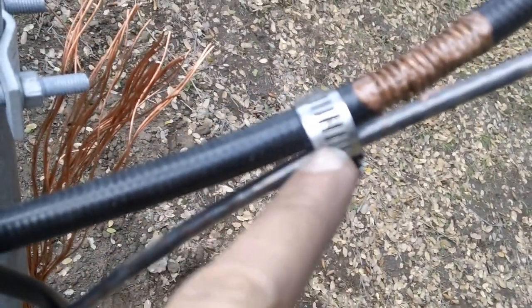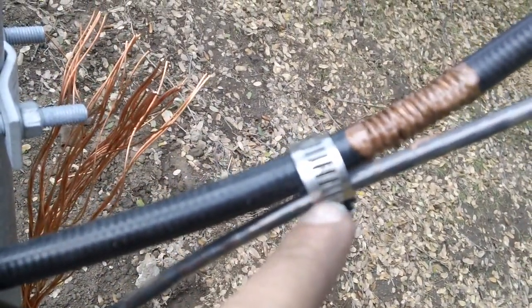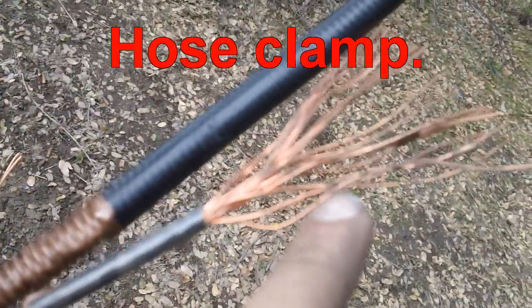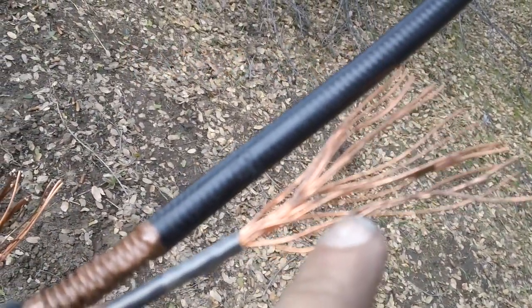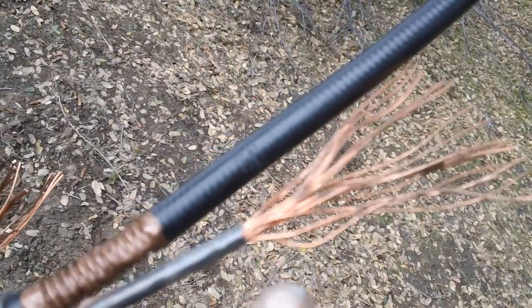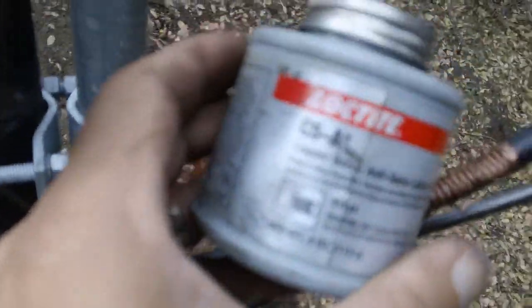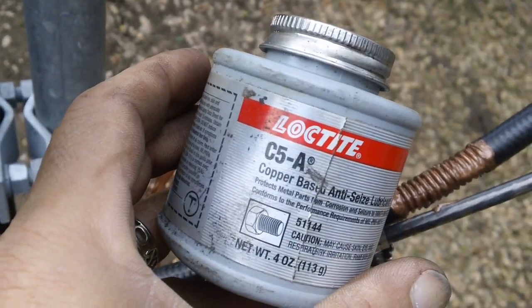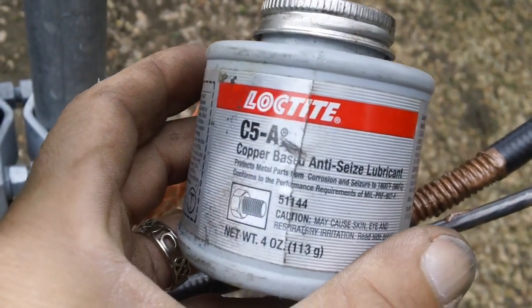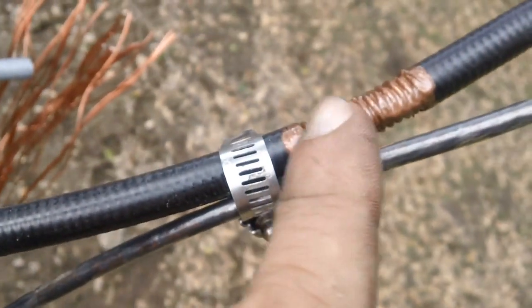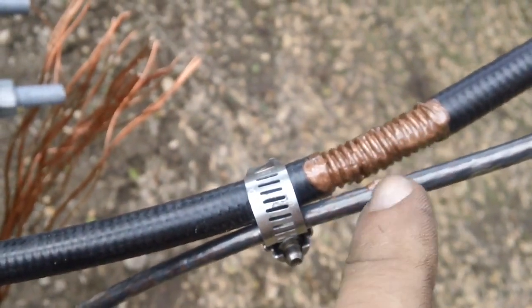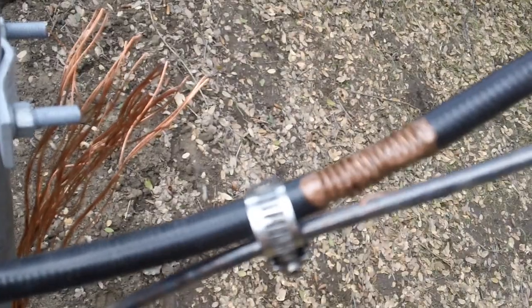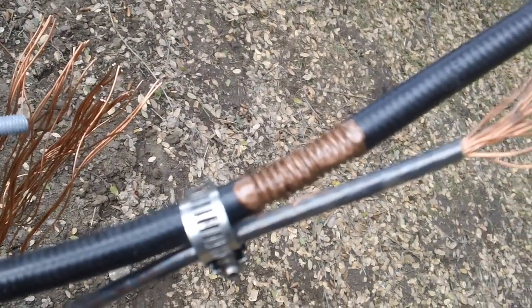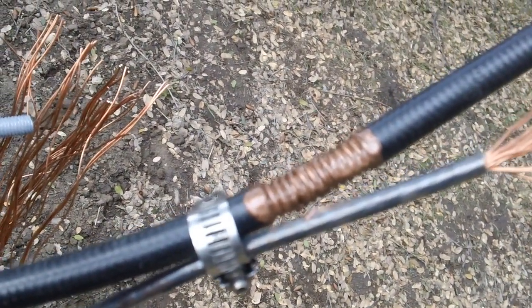So what you see here is my pipe clamp, size 8 gauge cable, and I have it fanned out, with the center conductor, or the outer shield of the cable, coated with copper coat, C5-A copper based anti-seize lubricant. It'll help prevent this from being corroded, and it also has copper flakes or dust in it for maximum conductivity.